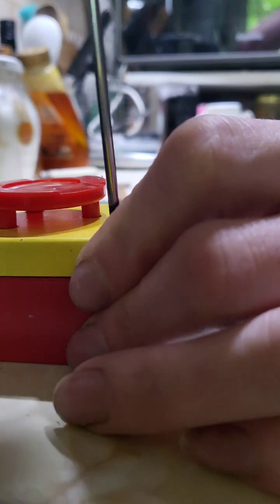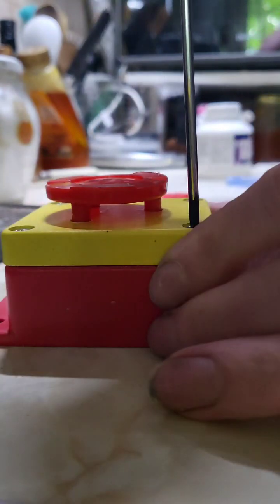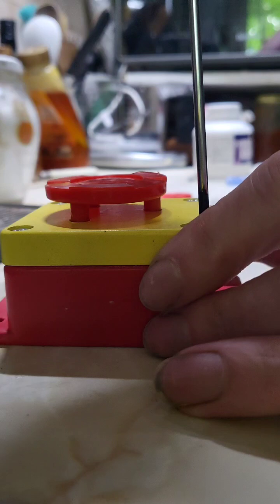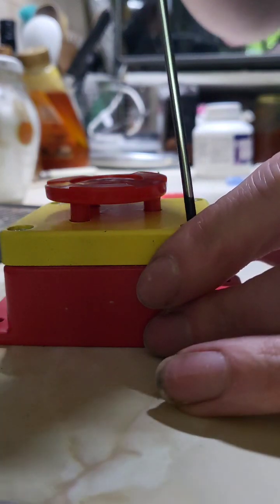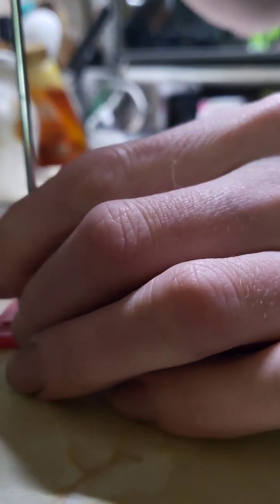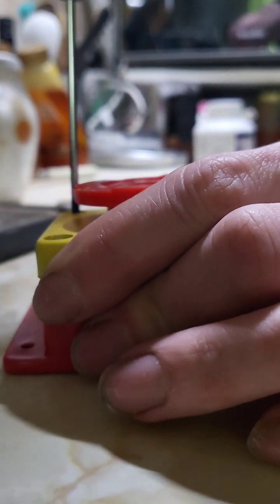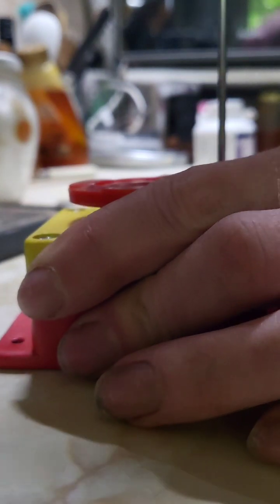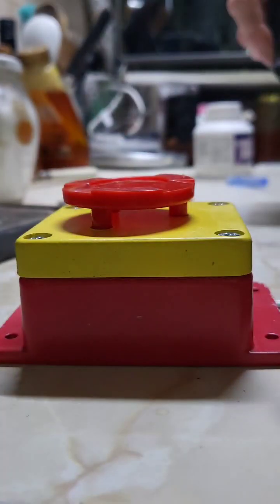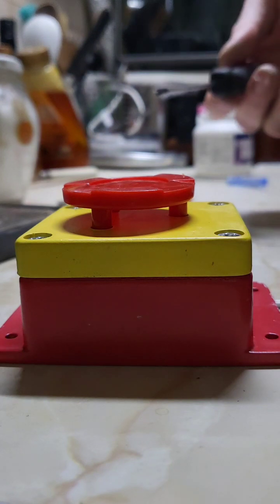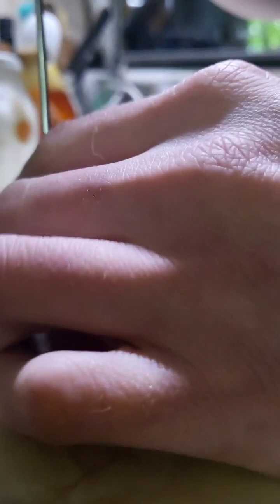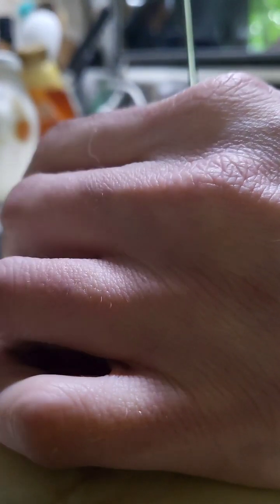You don't want to hammer down on these too far. Go around in circles, tightening each one by one, and you can feel when it bites. Don't do one by itself, otherwise there'll be too much pressure and you might create an uneven joint somewhere, leading to water ingress. So you go around in circles, tightening a little more as you go, and eventually they'll all get finger tight, which will be fine because I've got Loctite on here.